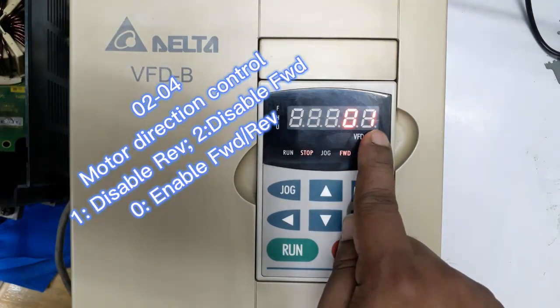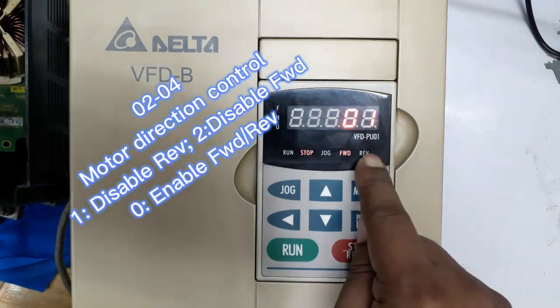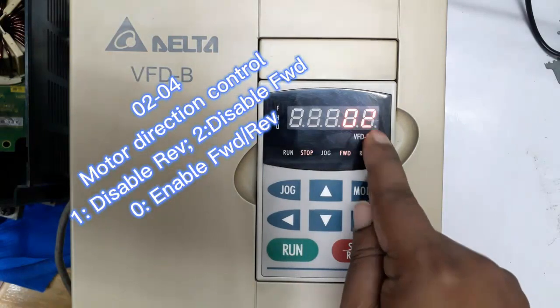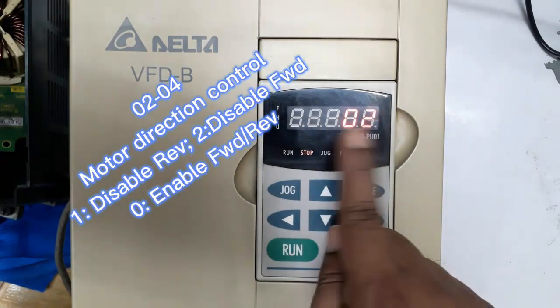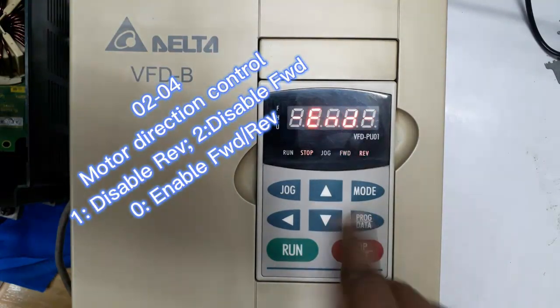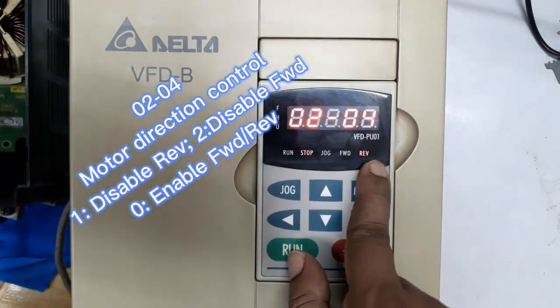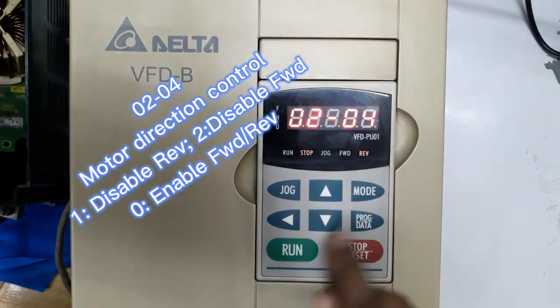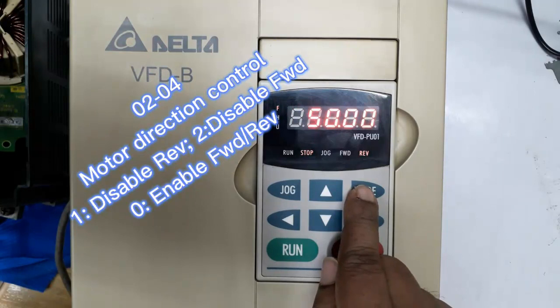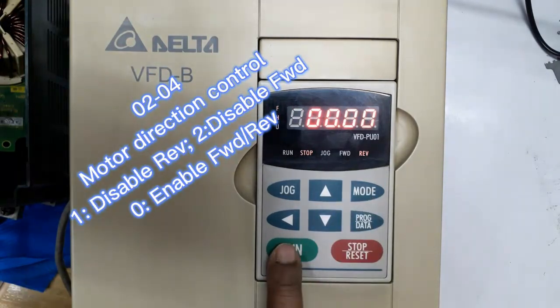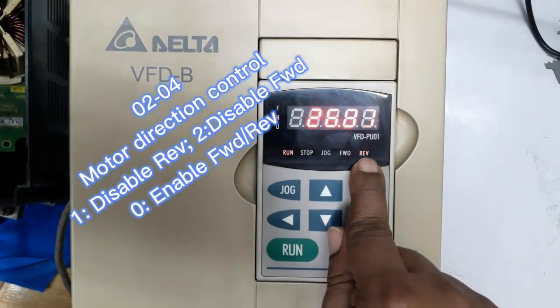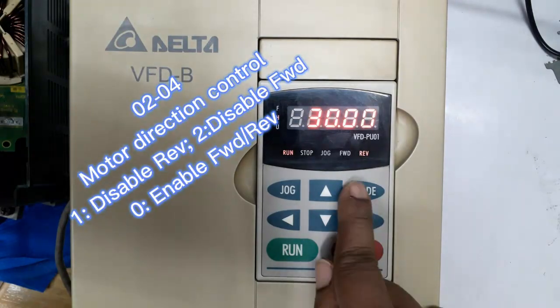If you set 1, reverse rotation will be disabled, and if set 2, forward rotation will be disabled. So we set 2 here, that means now only reverse rotation will be allowed.